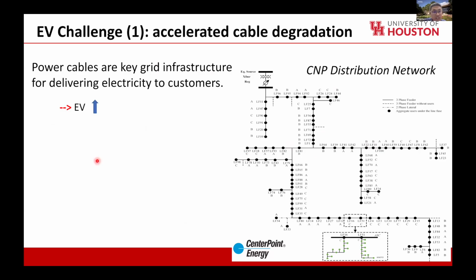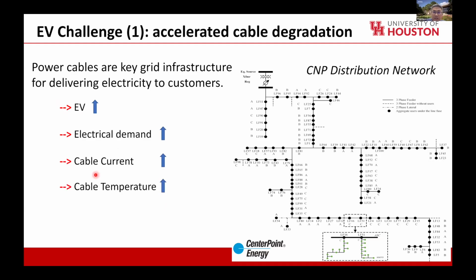The challenge here is when we have a lot of EVs, they charge and increase the electrical demand. Then the cables and power lines will need to carry a greater current, which increases the cable conductor temperature. With higher conductor temperature, it leads to faster degradation, meaning we may have to replace some cables much sooner than expected.